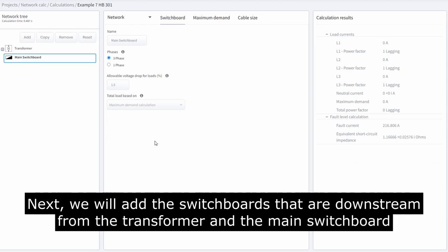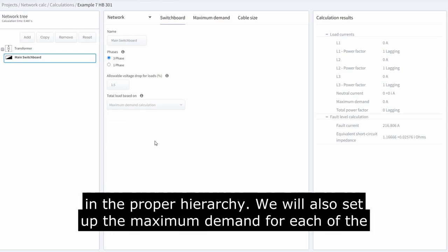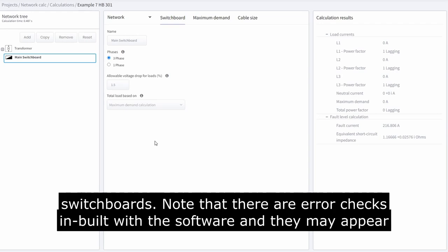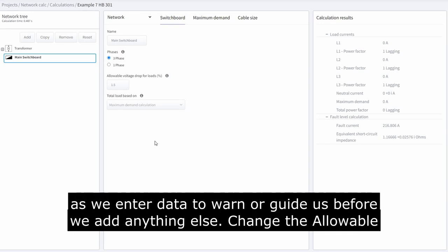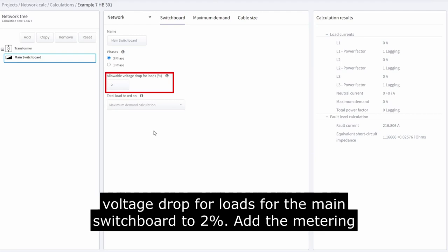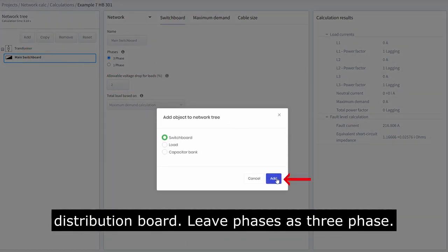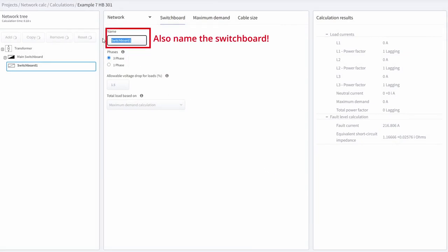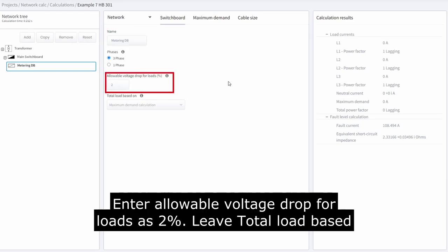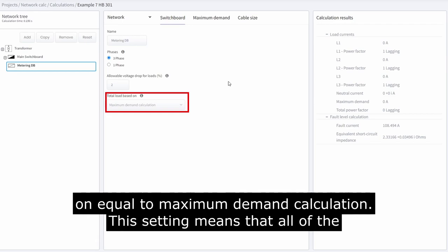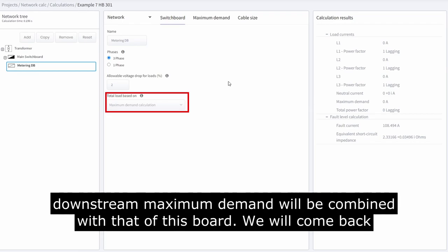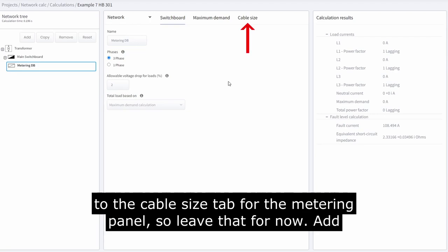Next, we will add the switchboards that are downstream from the transformer and the main switchboard in the proper hierarchy, and set up the maximum demand for each switchboard. Note that there are error checks built into the software that may appear as we enter data. Before we add anything else, change the allowable voltage drop for loads for the main switchboard to 2%. Add the metering distribution board, leave phases as 3-phase, and enter allowable voltage drop for loads as 2%, leaving total load based on equal to maximum demand calculation. We will come back to the cable size tab for the metering panel.